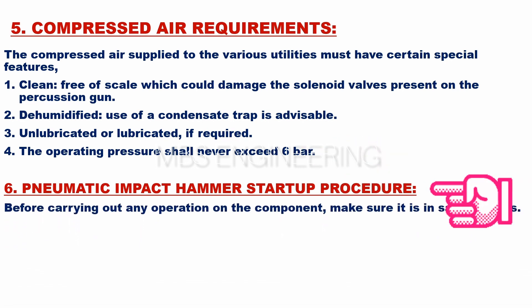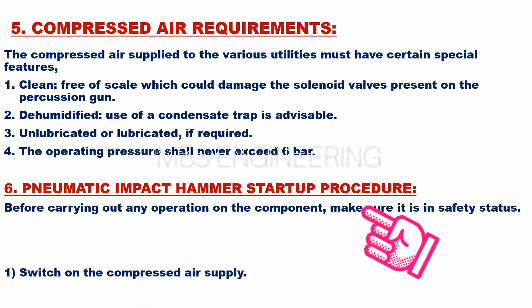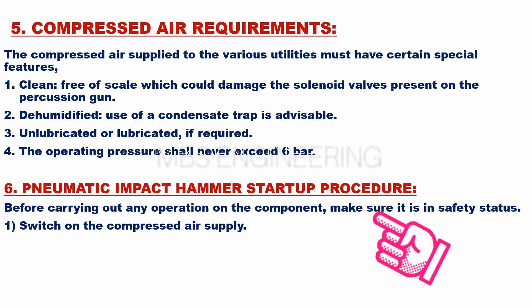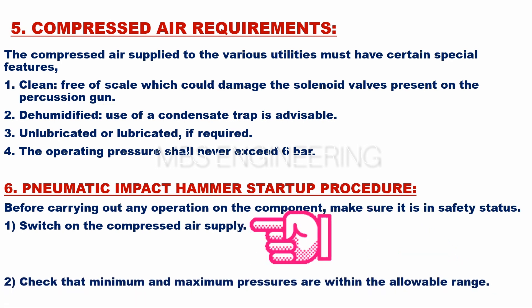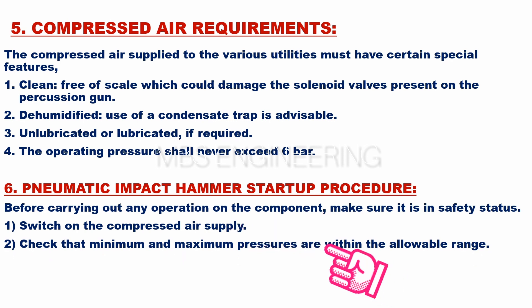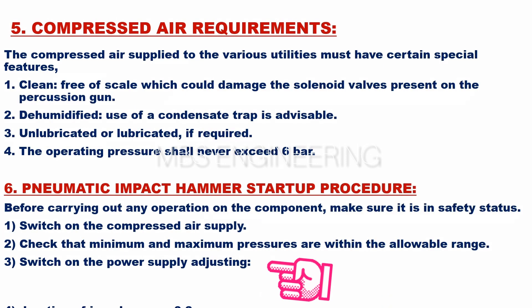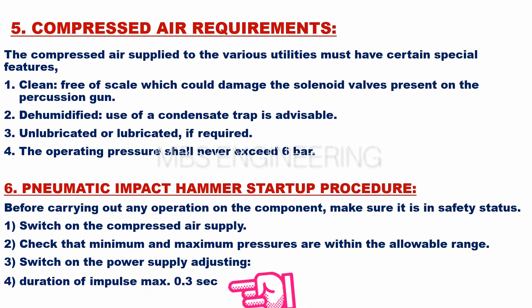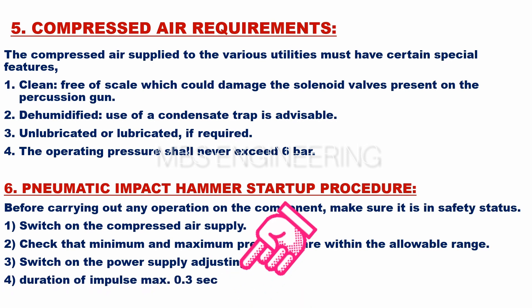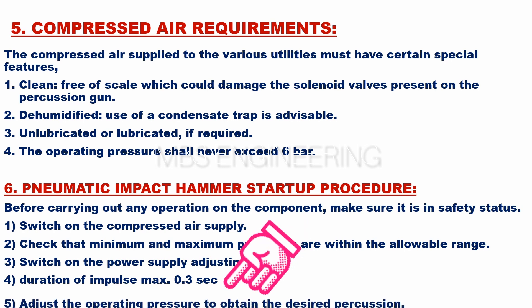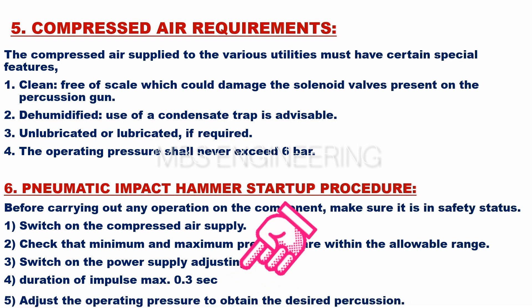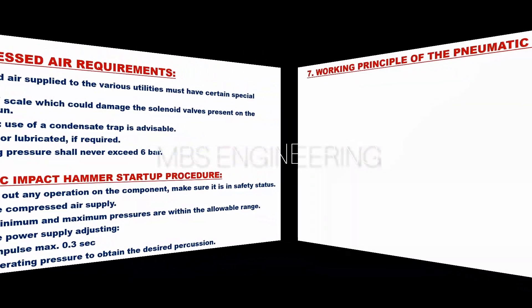Before carrying out any operation on the component, make sure it is in safety status. The first step is to switch on the compressed air supply. The second step is to check that minimum and maximum pressures are within the allowable range. The third step is to switch on the power supply. The fourth step is the duration of impulse — maximum 0.3 seconds. The fifth step is to adjust the operating pressure to obtain the desired percussion.